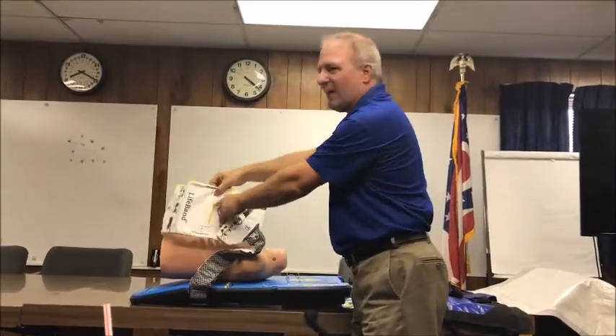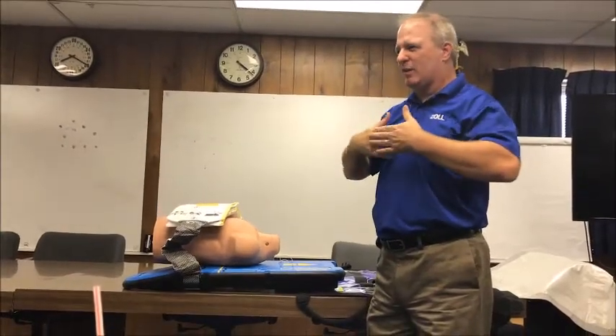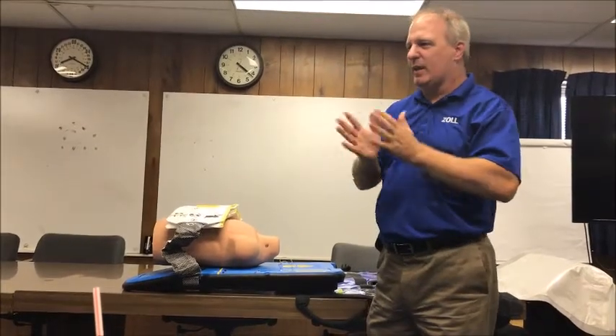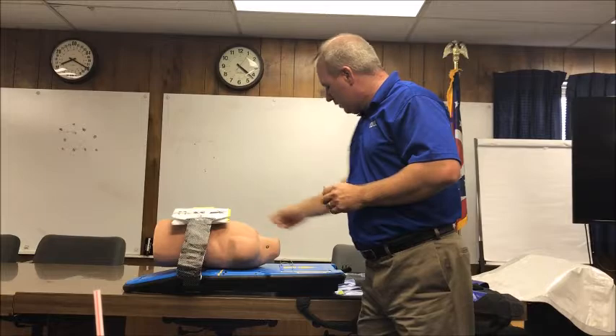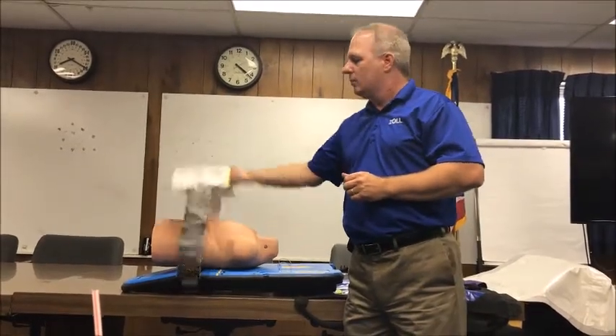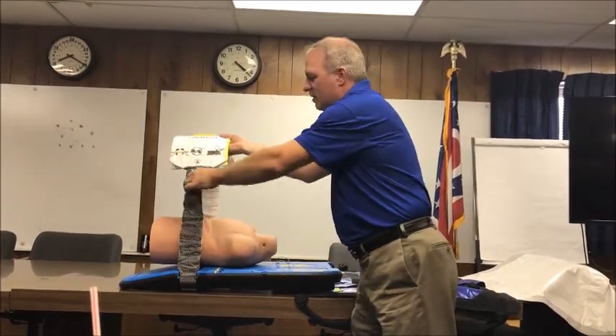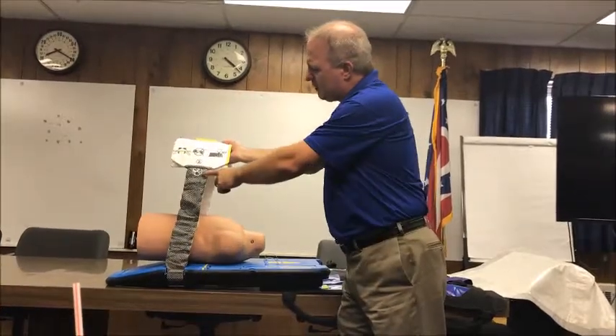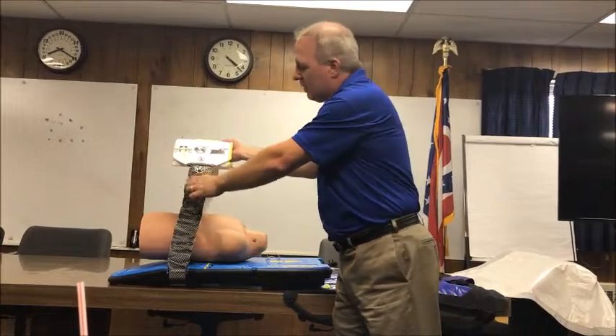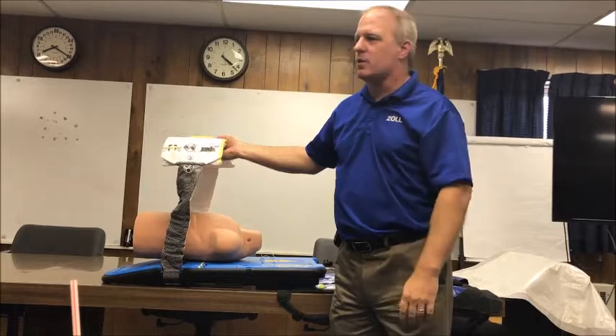You'll see there's a piece of yellow plastic that sticks up here. The band has Velcro on it, but Velcro over time can certainly wear. So that yellow piece of plastic helps to make sure that everything's nice and tight and snug and lined up where it should be. So once you align the band on the patient's chest, all you want to do is pull up. Make sure there's no slack. And do a quick visual on both sides, make sure that the band is not twisted. Everyone says, couldn't you come up with something a little bit better looking than this? Couldn't you do like a Zoll blue or something? This is designed so if there's a twist, it's blatantly obvious whether you're colorblind or whether you're normal vision.